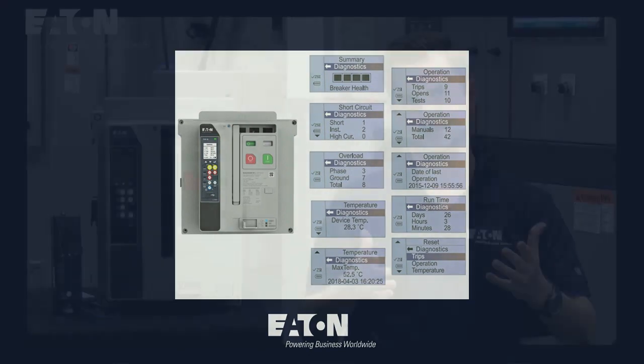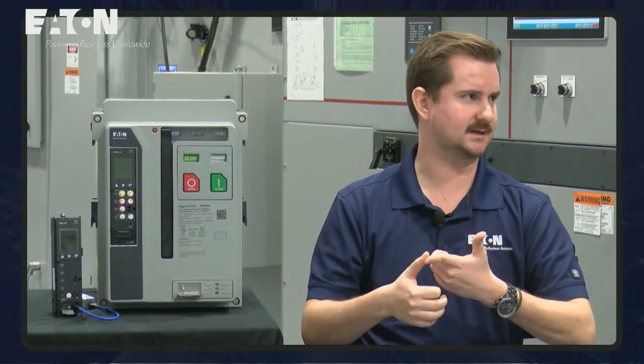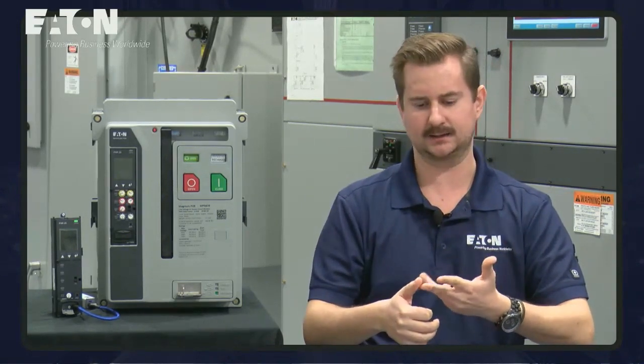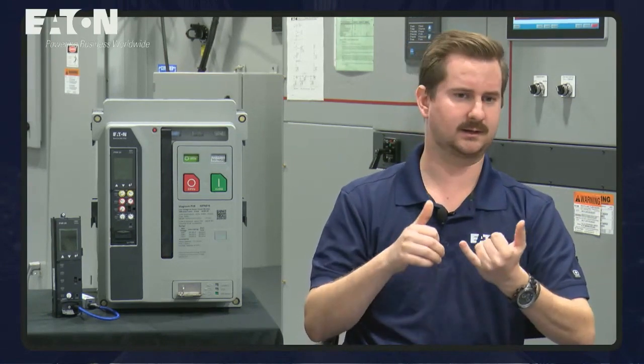Okay, that's great. So I keep hearing about this breaker health feature that we have in PXR trip units. Can you tell us more about that, please? Yeah, some of you out there may be familiar with breaker health already if you're familiar with our Power Defense molded case circuit breaker line. This is another addition of that just for our Magnum air circuit breakers. Breaker health is an algorithm that was developed by Eaton. It's looking at several different parameters that include the temperature of the contacts in the breaker, how many operations it's had, how many faults it's seen and cleared, how many overload events it's had, and how long it's been operating.